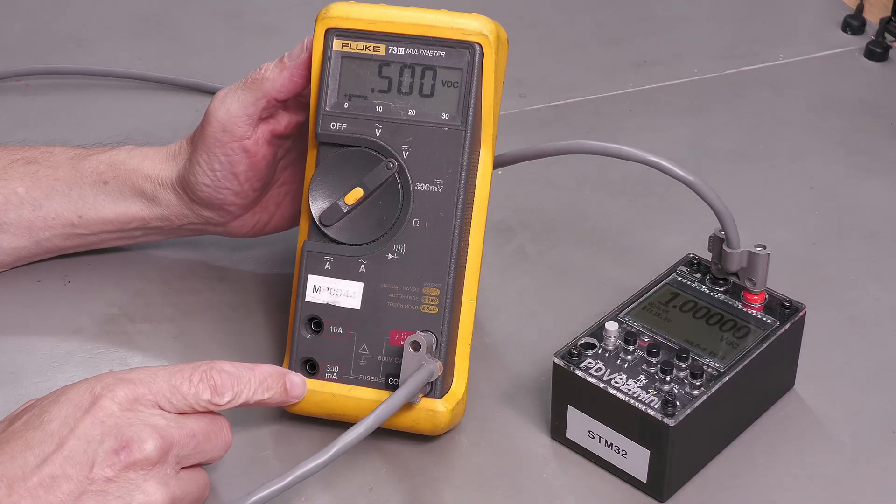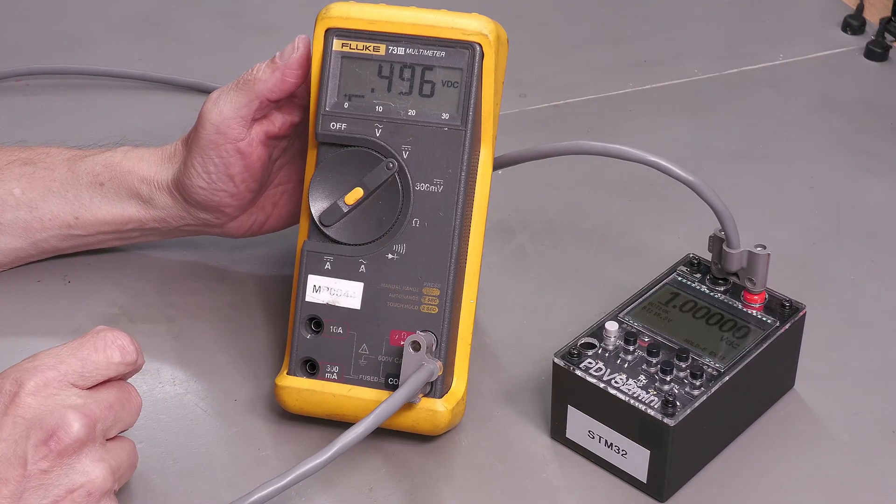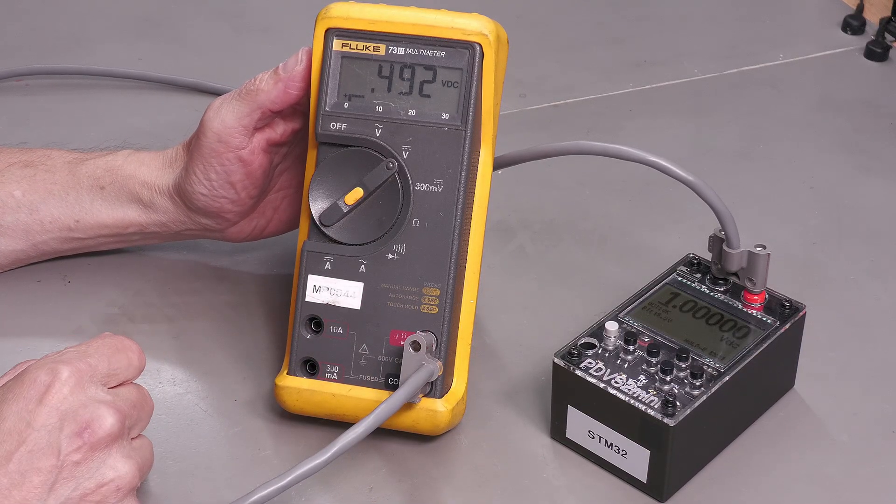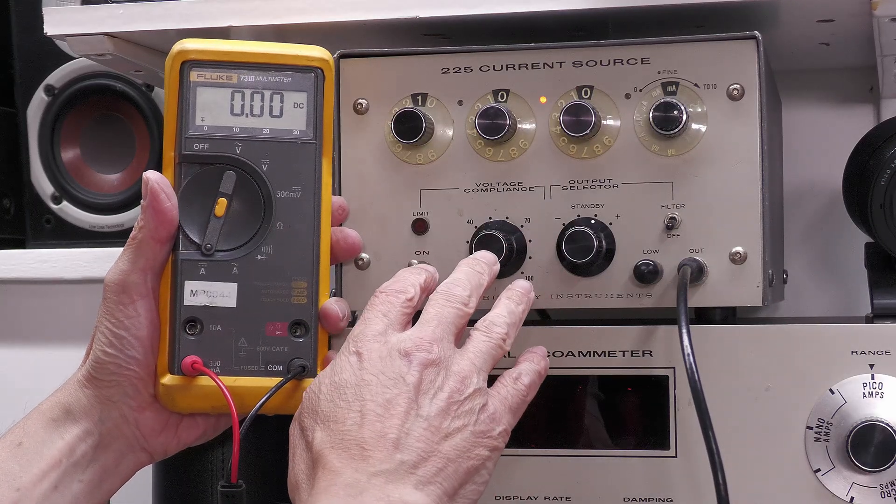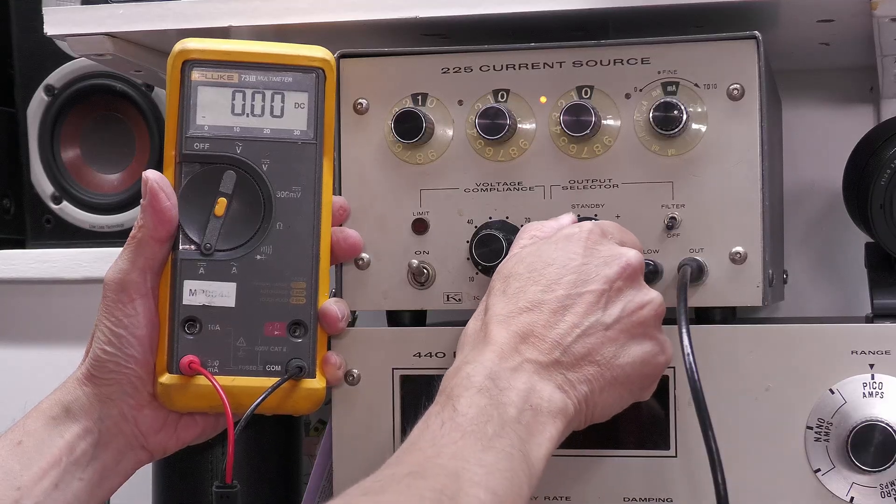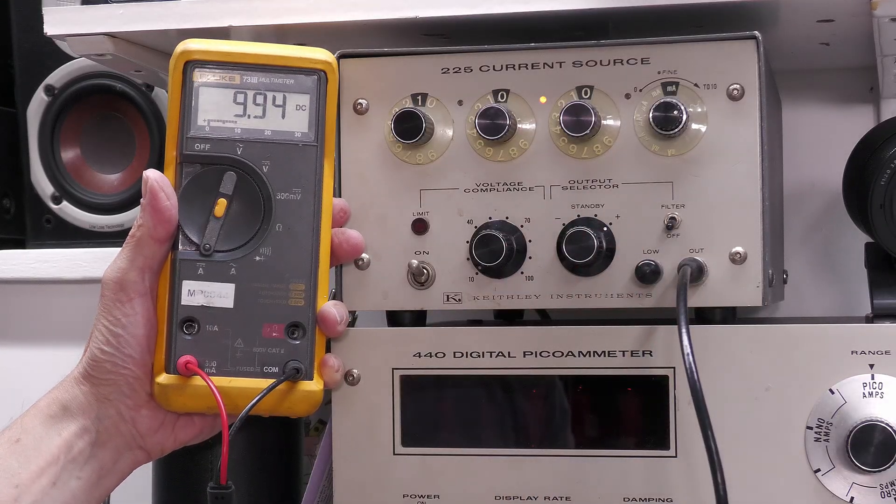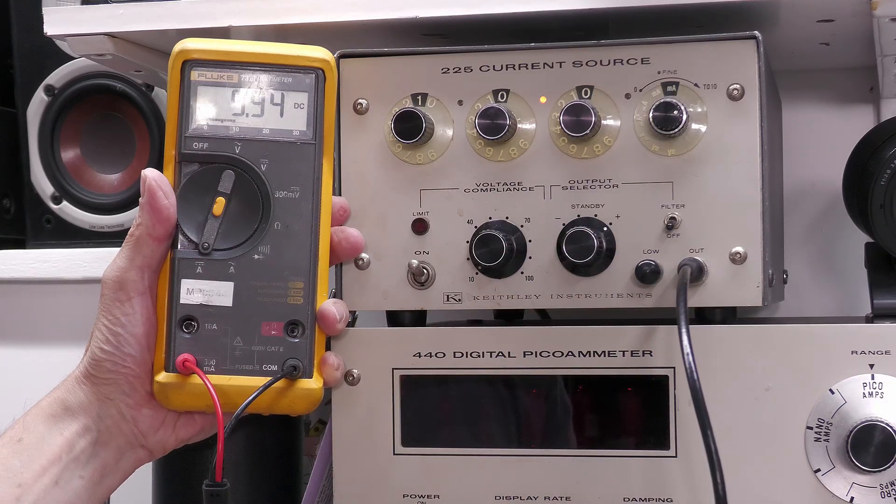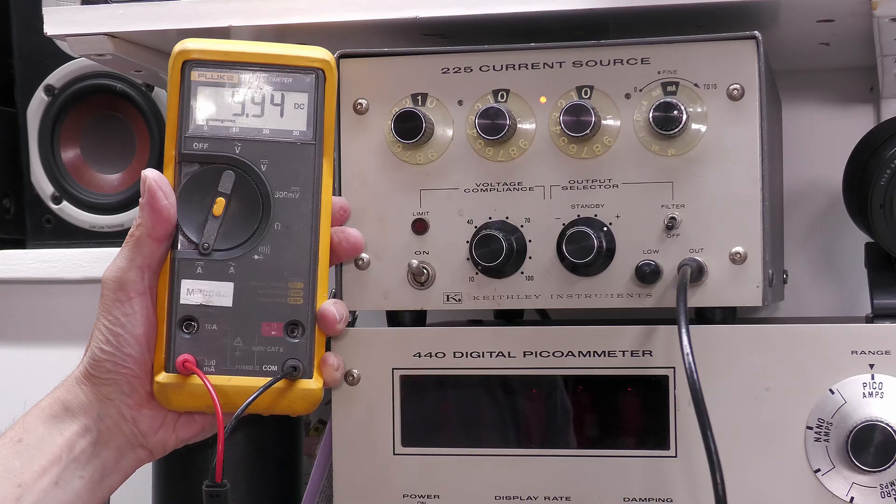How about the current inputs? Let's stick it on my current source and see what it does. Okay I've got hooked up the current source. I've set 10 milliamps output so let's just put it on see what we get. That's not too bad - 9.94.